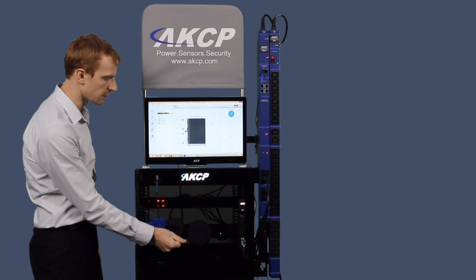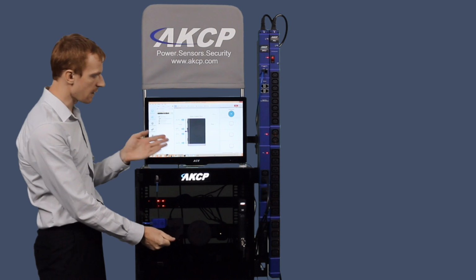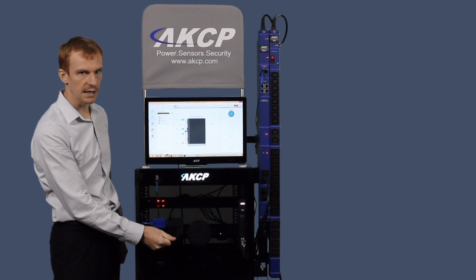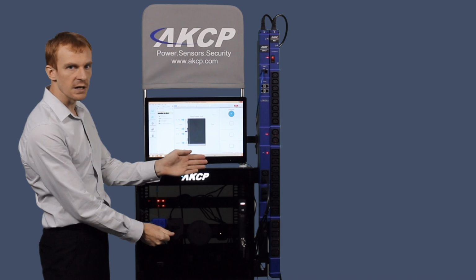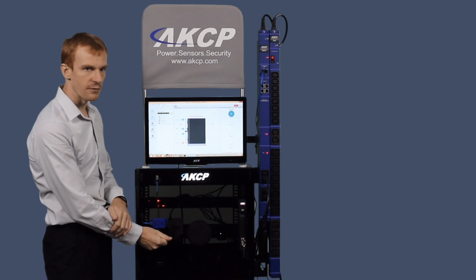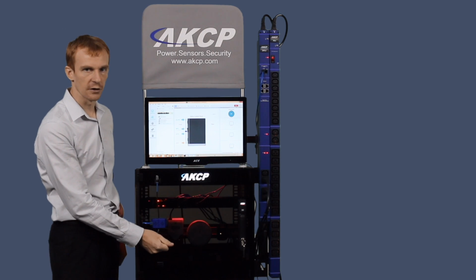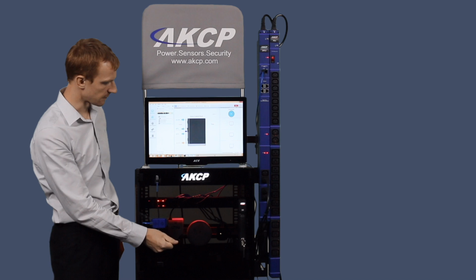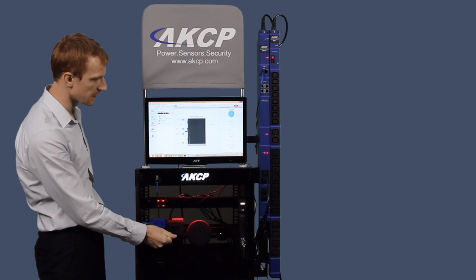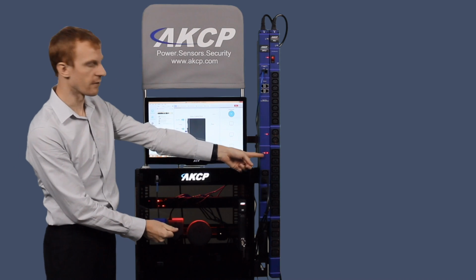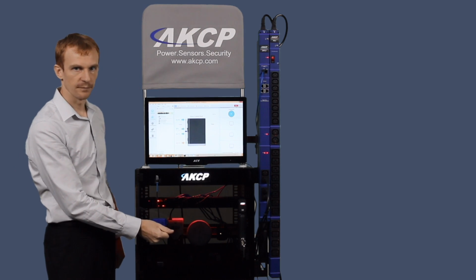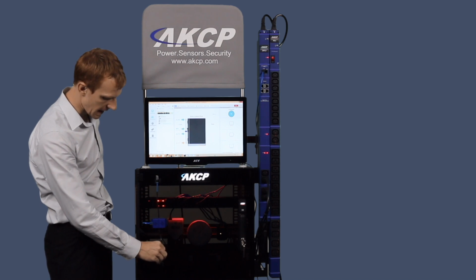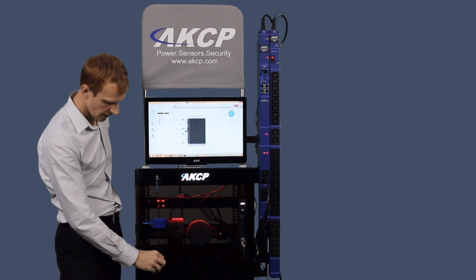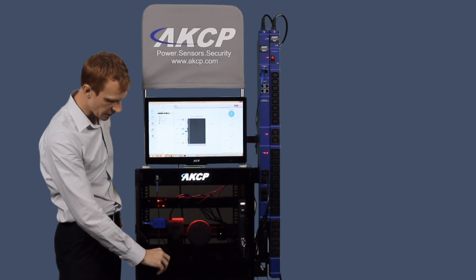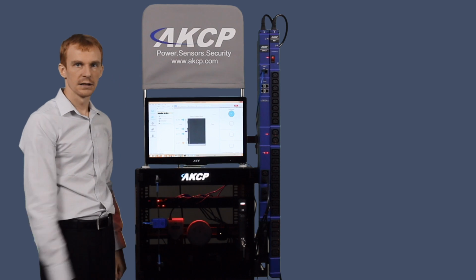I will do this by holding the temperature sensor in my hand, and when we reach 25 degrees on the air inlet, the SPC Plus will turn on our red light to simulate the turning on of a cooling system inside the cabinet. You can see that that has happened now, and the relay on our SPC Plus has turned on. When the temperature returns back to a normal condition, the relay will turn off, turning off our red light and our cabinet cooling systems.